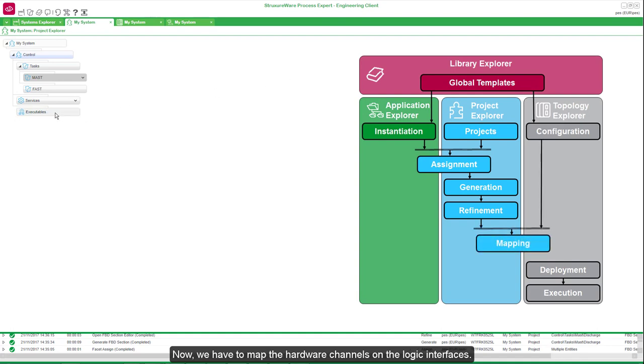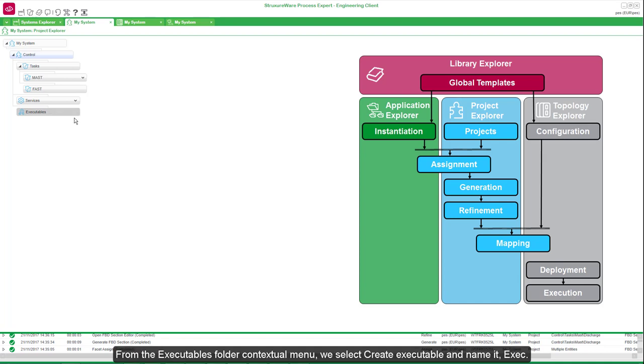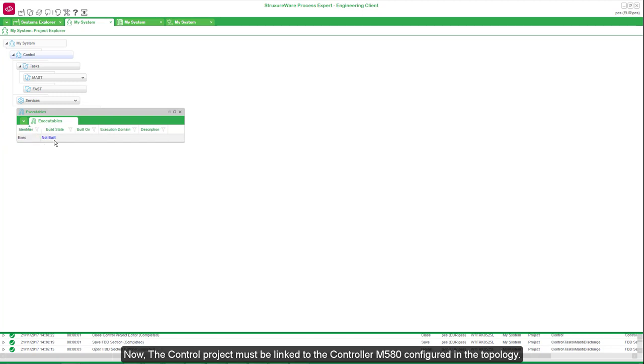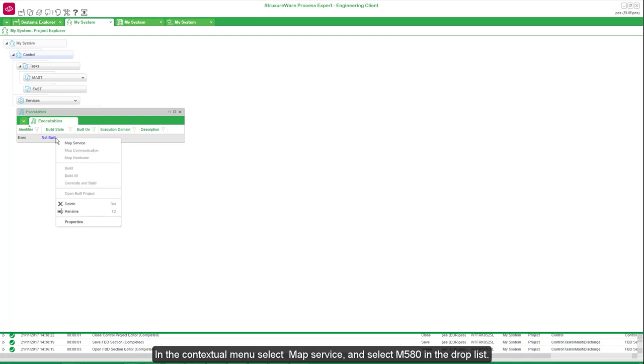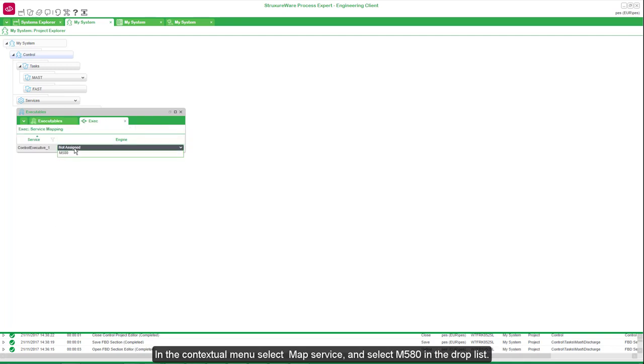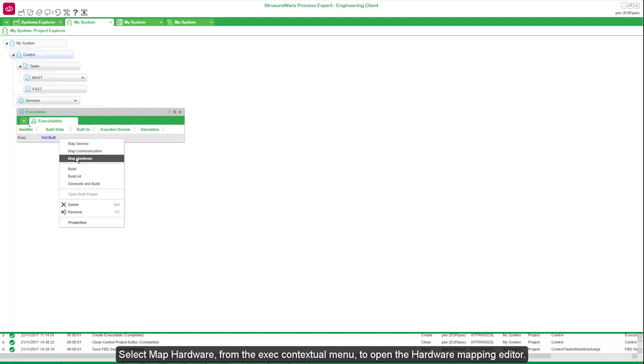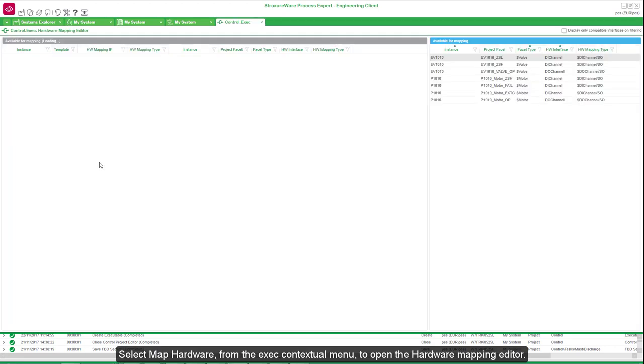Now we have to map the hardware channels on the logic interfaces. From the Executables folder contextual menu, we select Create Executable and name it exec. The control project must be linked to the M580 controller configured in the topology. In the contextual menu select Map Service and select M580 from the drop list. Once the configuration is selected, the hardware mapping can be done. Select Map Hardware from the exec contextual menu to open the hardware mapping editor.